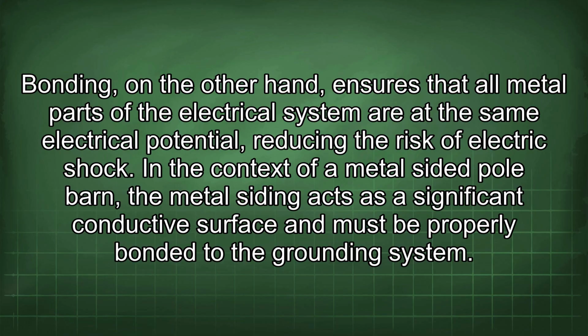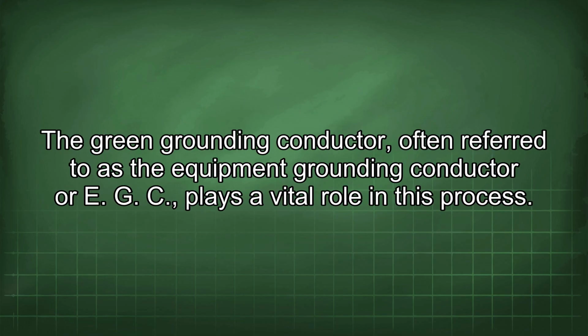In the context of a metal-sided pole barn, the metal siding acts as a significant conductive surface and must be properly bonded to the grounding system. The green grounding conductor, often referred to as the equipment grounding conductor or EGC, plays a vital role in this process.